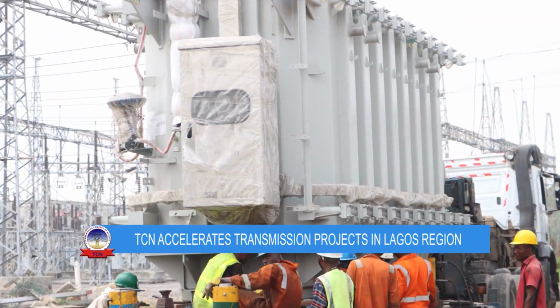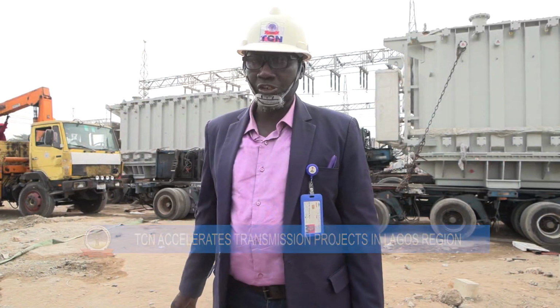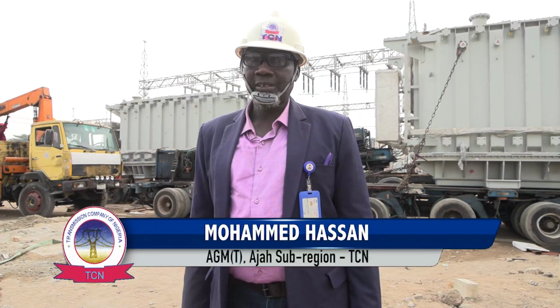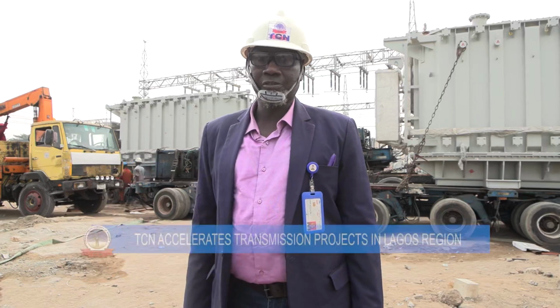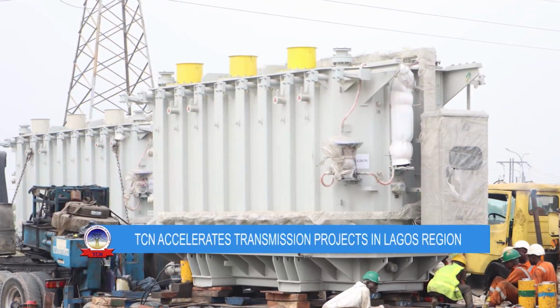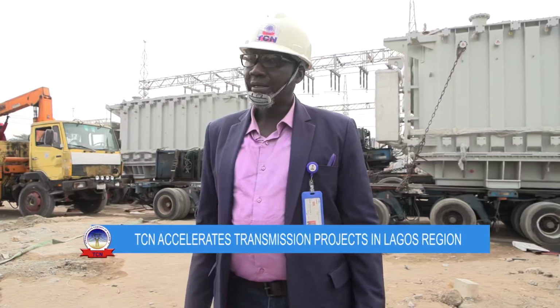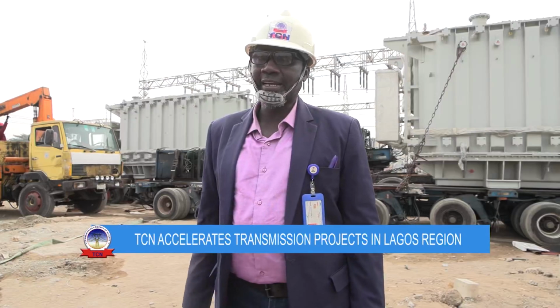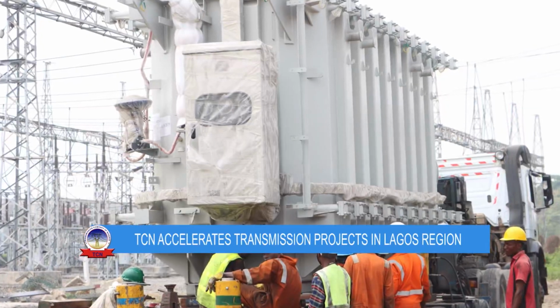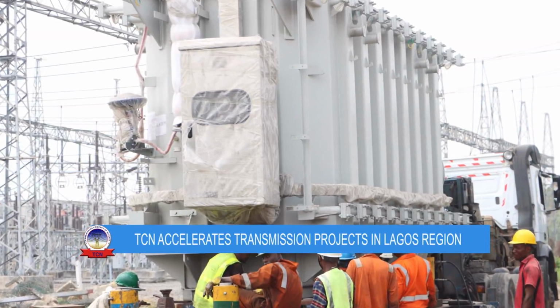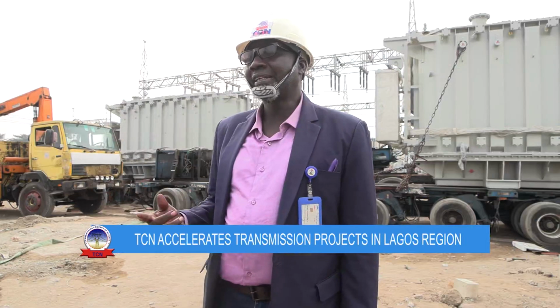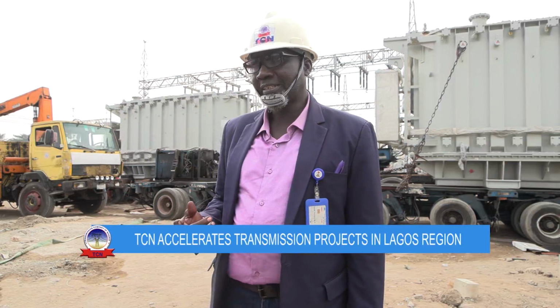Two transformers are going to be installed here at Alagbon to expand under the transmission expansion. We are expected to have about 6 feeders out of these transformers after installation. So if we add it up, it's going to be almost 300 MVA, more than 300 MVA capacity.